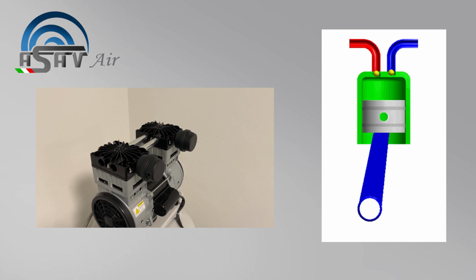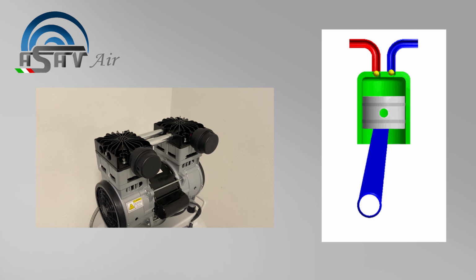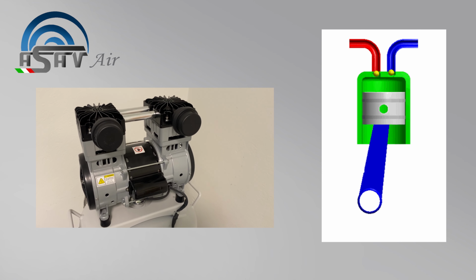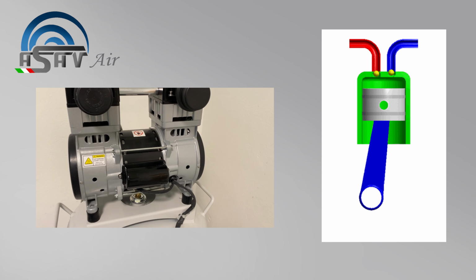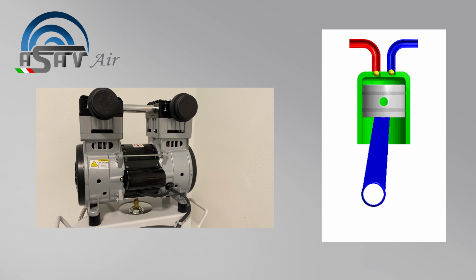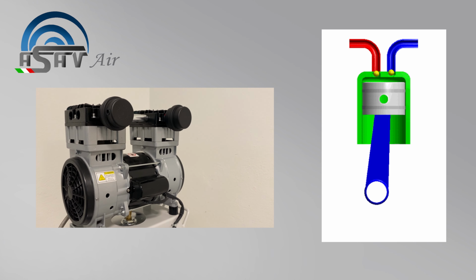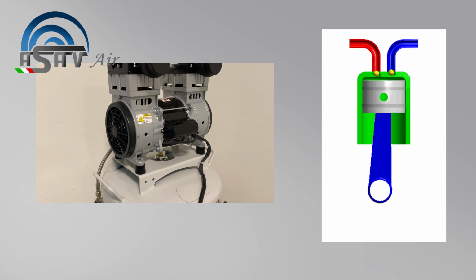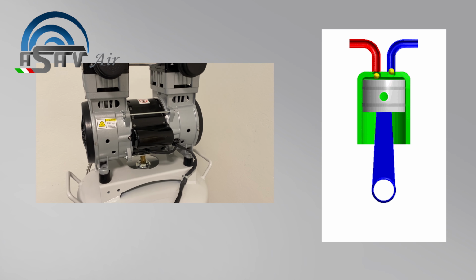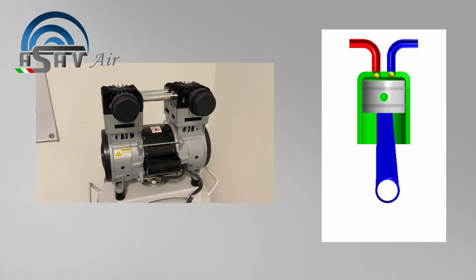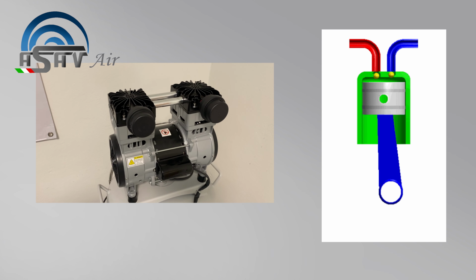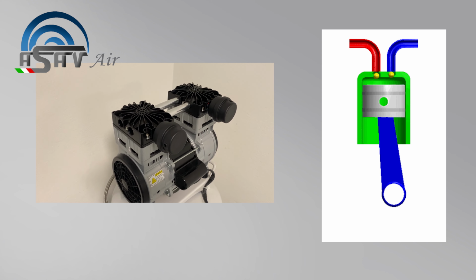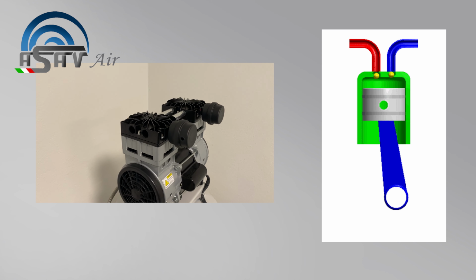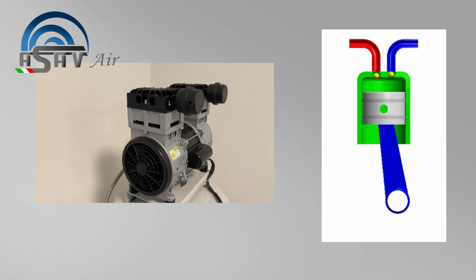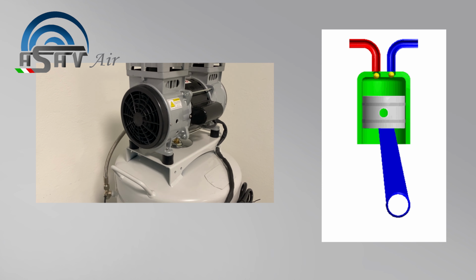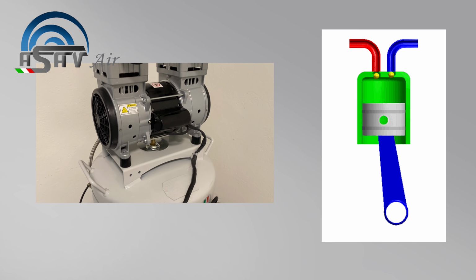As the piston moves upwards, the air above it is compressed and it keeps the inlet valve closed and pushes the exhaust valve open. The air moves from the exhaust port to the tank. With each stroke, more air enters the tank and the pressure increases. The oil-free piston compressor does not inject oil into the compressor chamber, as it does not contain oil but has Teflon sealing rings that do not need lubricant.